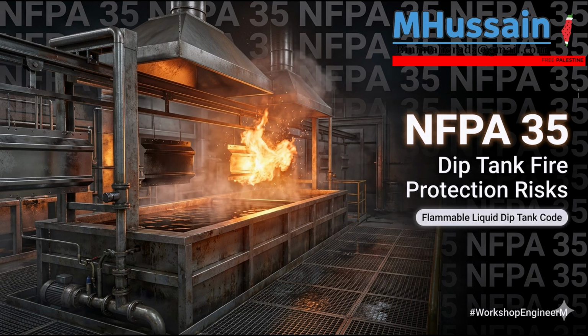Now, with all these vapors present, the electrical systems become a massive ignition risk. NFPA 35 points heavily to NFPA 70, the National Electrical Code, to dictate hazardous area classifications. And those classifications map perfectly to the physical behavior of the chemicals. How so? Well, where Class I liquids are processed in open equipment, the area immediately surrounding that equipment is classified as Class 1, Division 1.